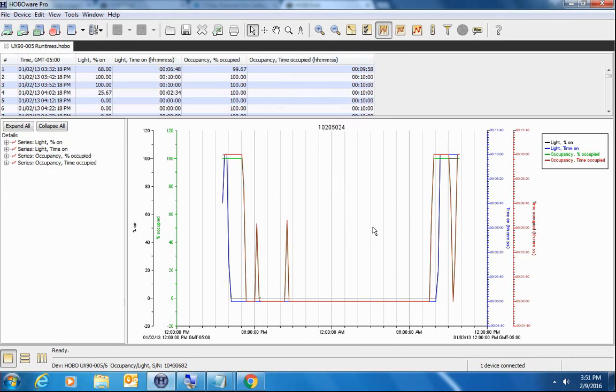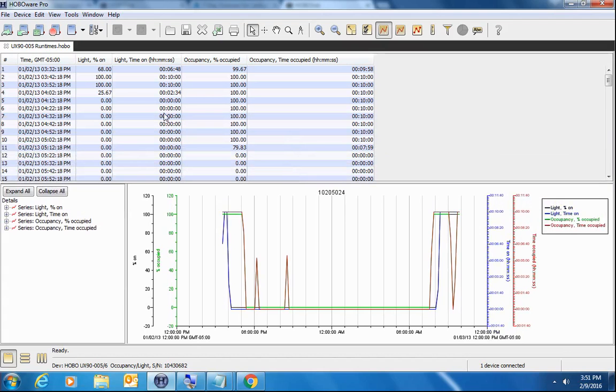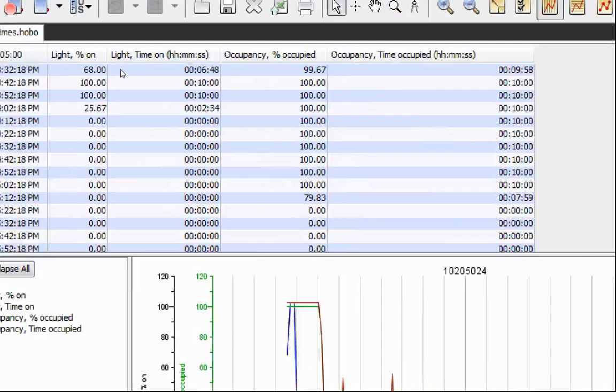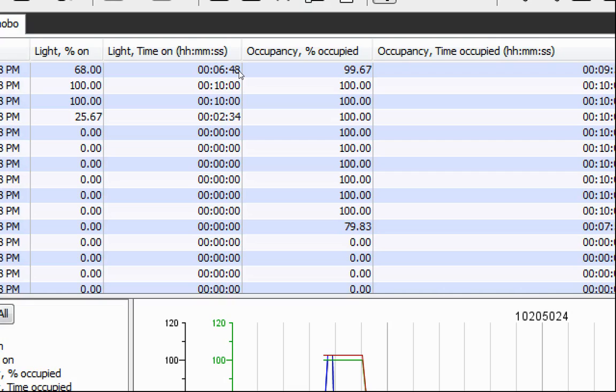And there's our data. Here's our XY plot, which is percent of time per interval. This is actual time per interval that it was occupied versus on. The tabular data is a little bit easier to understand. So what you see in each 10 minute logging interval, for example, the lights were on 68 percent of the time during that 10 minute period that equates to six minutes and 48 seconds of on time versus the occupancy. The percent of time it was occupied during that period was 99.67 or approximately nine minutes.